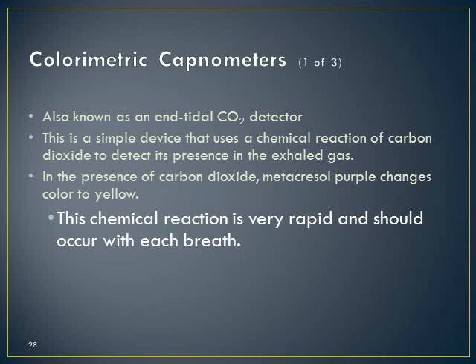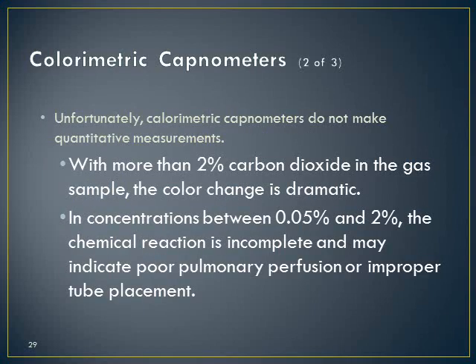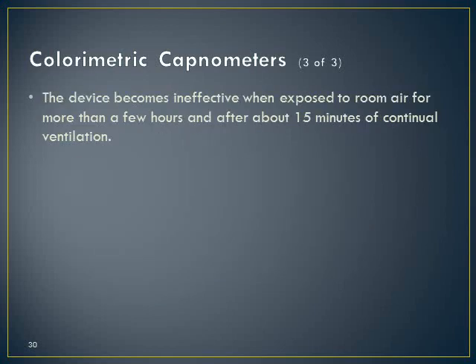The reaction is very quick, and it should occur as soon as you hook them up without any delay. They don't make quantitative measurements. That's the downside to colorimetric capnography. With more than 2% carbon dioxide in the gas sample, the color change is dramatic, so we know we're good. But even if we have a concentration of 0.5 or 0.05 to 2%, we may still get some color change. It'll just be incomplete, and it can be more confusing for us.